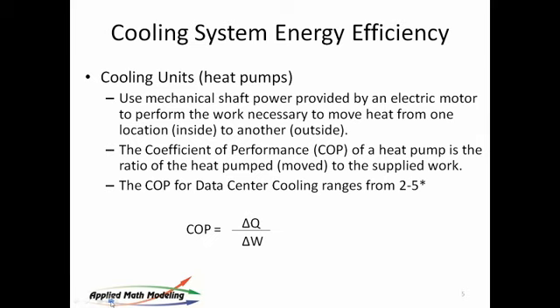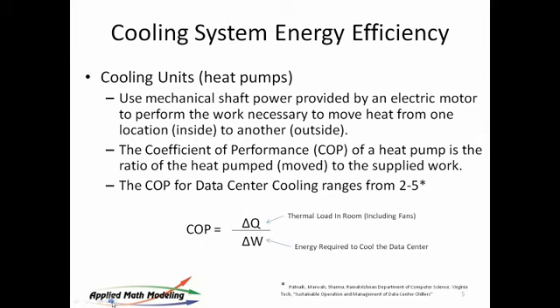And there is a relationship here that they use called coefficient of performance. The coefficient of performance is a ratio of the thermal load in the room, including the fans, which produce heat, divided by the energy required to cool the data center. It's this ratio that we're interested in.